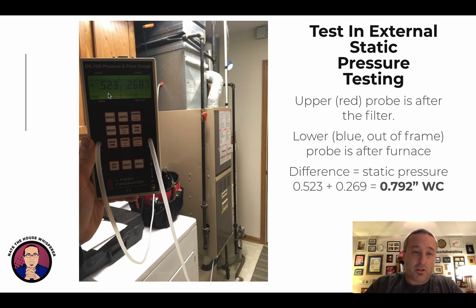So the static pressure, you can see there's 0.523 and then 0.2687. Even though this is negative, you look for the difference between them, how far apart are they. It's easiest to just add them, ignoring the negative symbols in front, just add them together. So we are at 0.792 inches of water column. This is well above the 0.5. This is an old PSC blower, it was probably fine, but this is not ideal. We can't run a modern ECM motor system with static that high without expecting some problems.